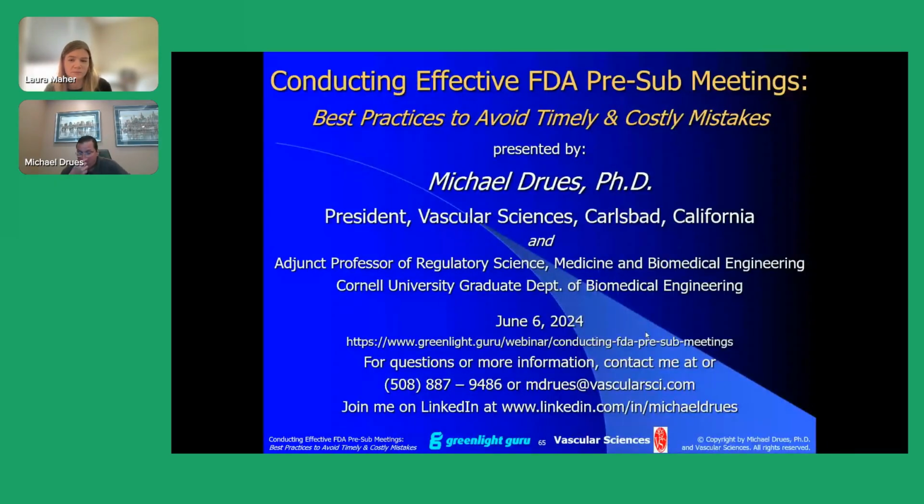Great question. I mentioned pre-sub supplements a little bit earlier. Just to reiterate, a pre-sub supplement gives you the opportunity to go to the FDA with additional information about one of the topics that you at least mentioned in your original pre-sub. The reason why a pre-sub supplement can be an advantage is because in some cases, not in all, it's a little quicker to go to the FDA with a pre-sub supplement.